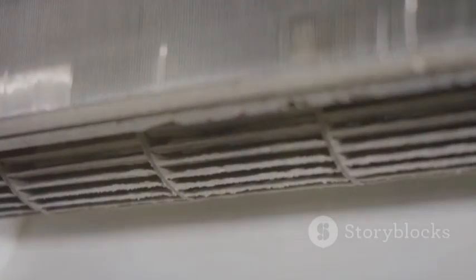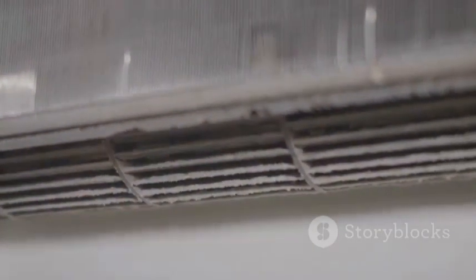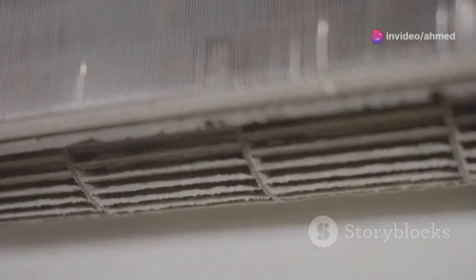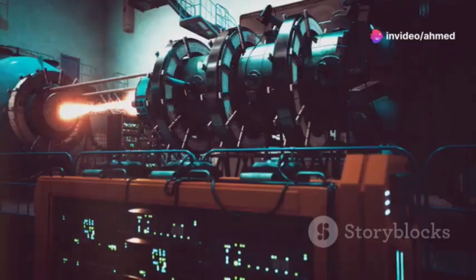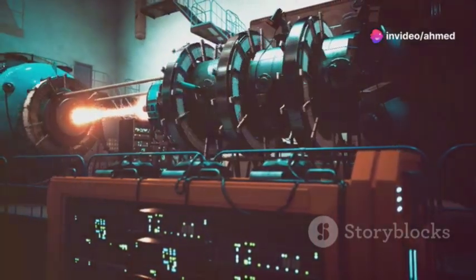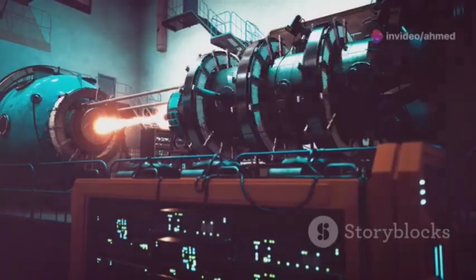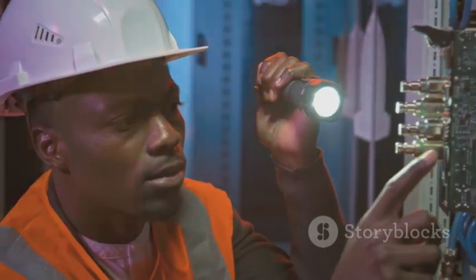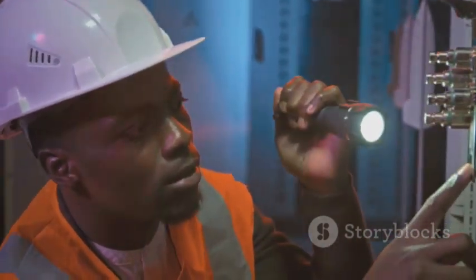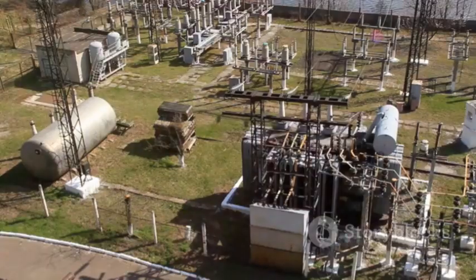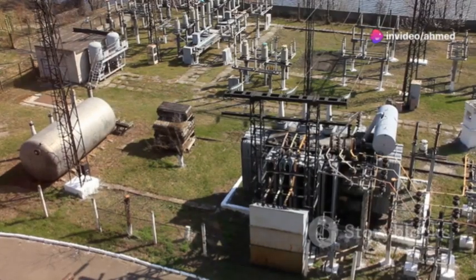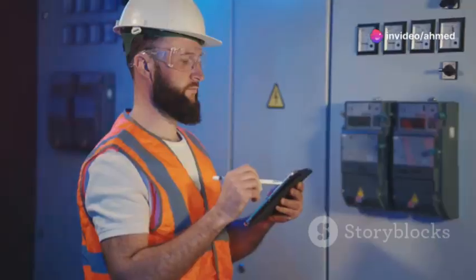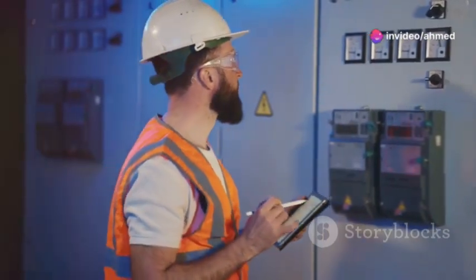It's a critical task, because a buildup of dust, dirt, and grime can lead to dangerous short circuits and even fires. Imagine the chaos if a power plant or a hospital lost power because of a dirty switchgear. Live cleaning is a specialized job, requiring expert knowledge and strict safety protocols. We're talking about dealing with thousands of volts here, so there's no room for error. But don't worry, we'll walk you through the entire process step by step.